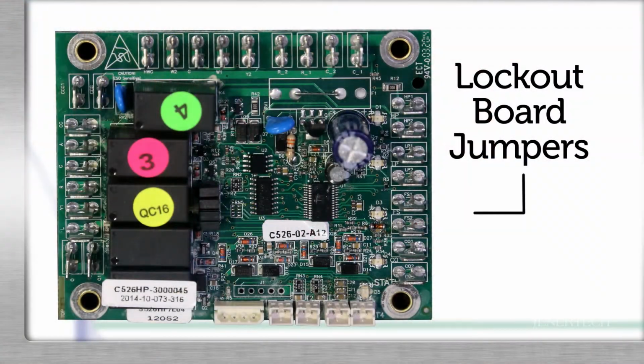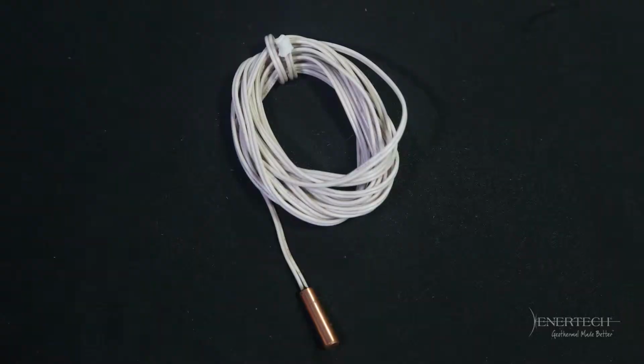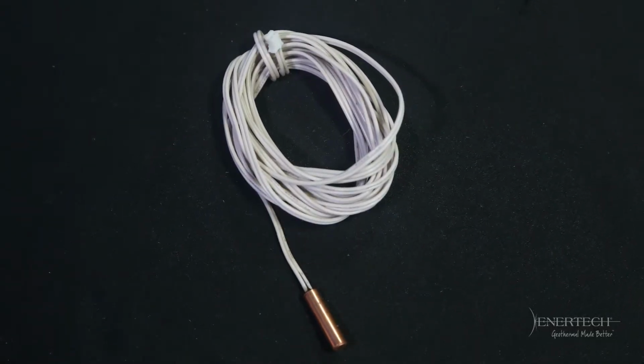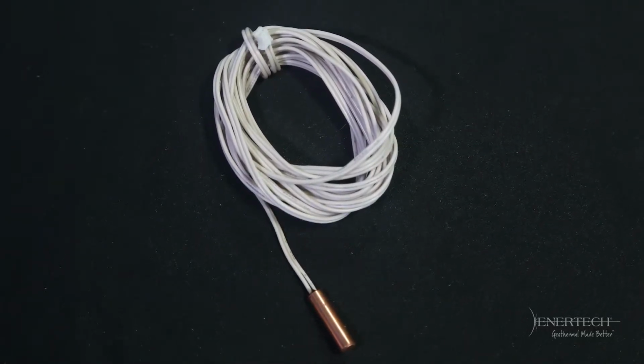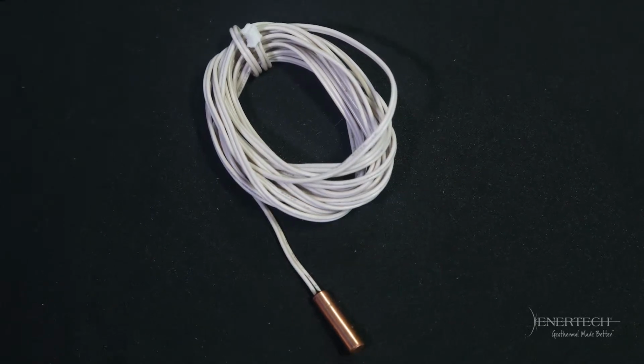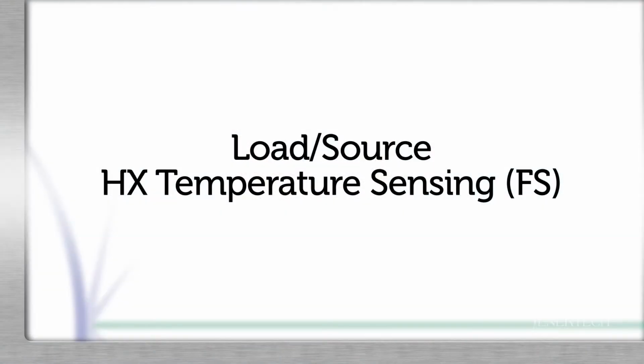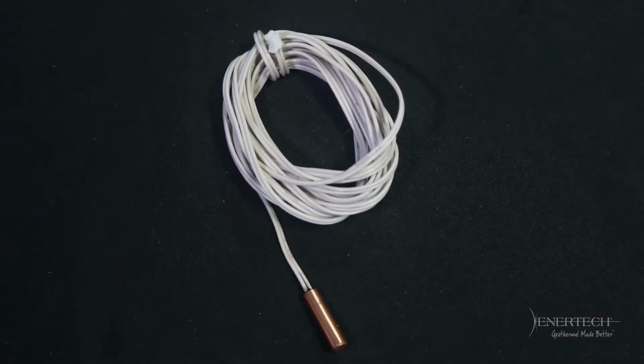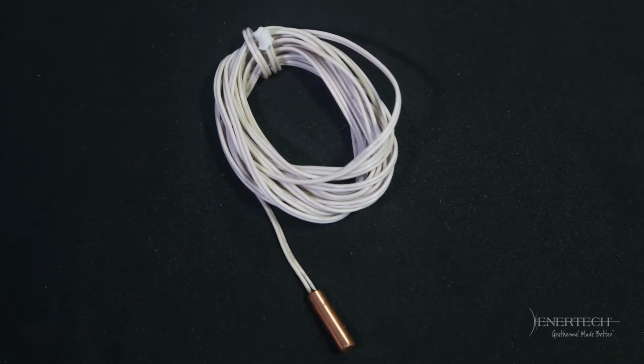The lockout board includes 4 jumpers for field selection of various board features. When the FS jumper is installed, with the T1 and T4 monitored and FS terminals ignored, the board operates in the load and source heat exchanger temperature sensing mode, which is the factory setting. When the FS jumper is removed, a flow switch can be used on the FS terminals.